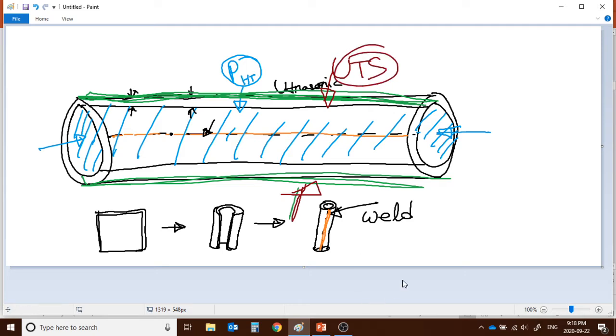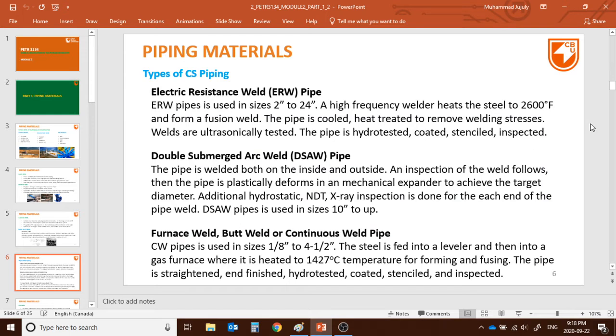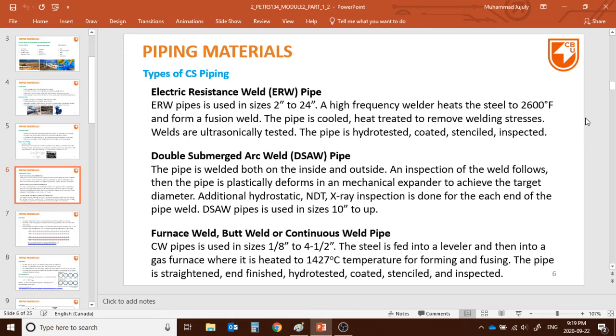For DSAW we usually do X-ray inspection, while for ERW we do ultrasonic inspection. DSAW pipe is used for sizes 10 inch and up. Furnace weld or continuous weld (CW) pipe is used from 1/8 to 4.5 inch — the steel is fed into a gas furnace heated to high temperature for forming and fusing. Then the pipe is finished, hydro-tested, coated, stenciled, and inspected. This covers all about carbon steel piping.